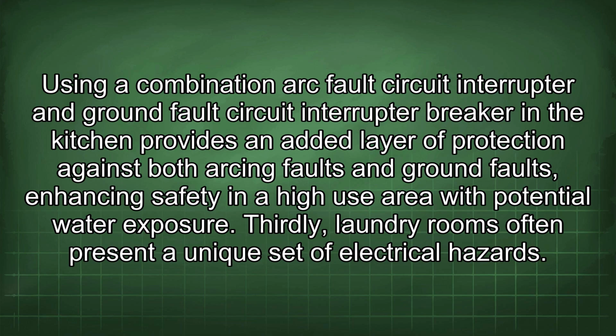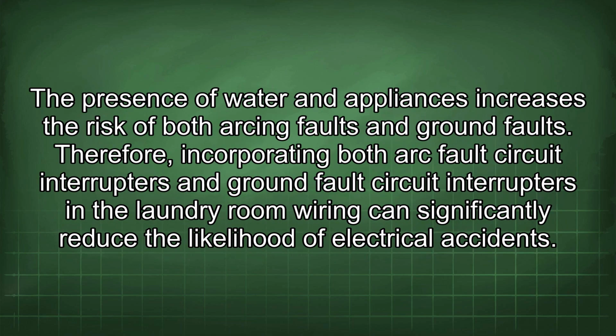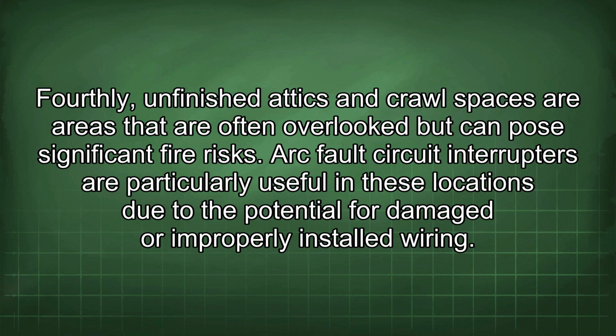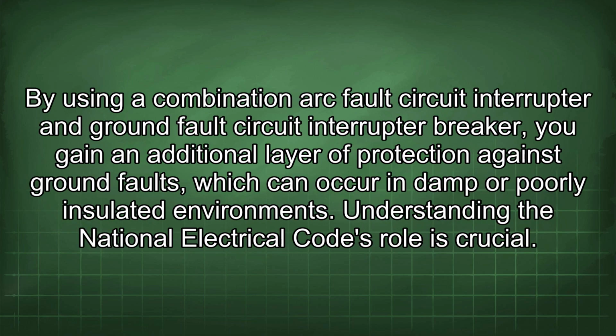Thirdly, laundry rooms often present a unique set of electrical hazards. The presence of water and appliances increases the risk of both arcing faults and ground faults. Therefore, incorporating both arc fault circuit interrupters and ground fault circuit interrupters in the laundry room wiring can significantly reduce the likelihood of electrical accidents. Fourthly, unfinished attics and crawl spaces are areas that are often overlooked but can pose significant fire risks. Arc fault circuit interrupters are particularly useful in these locations due to the potential for damaged or improperly installed wiring. By using a combination arc fault circuit interrupter and ground fault circuit interrupter breaker, you gain an additional layer of protection against ground faults, which can occur in damp or poorly insulated environments.